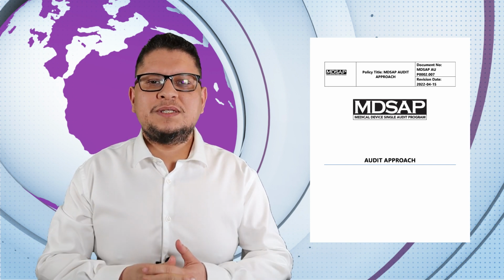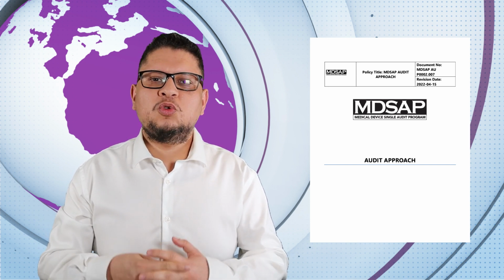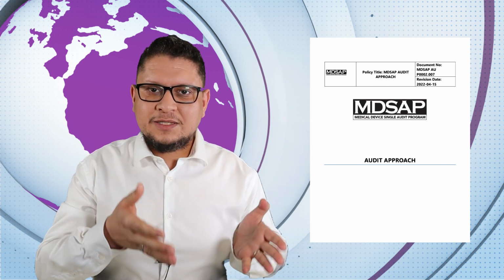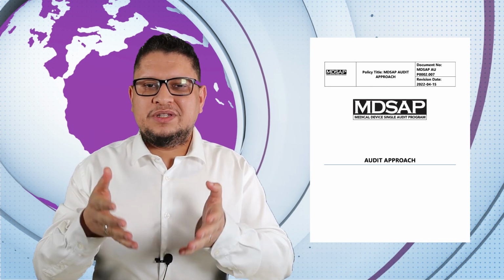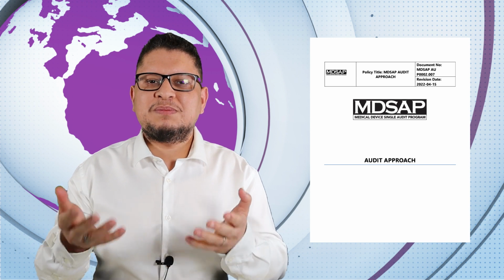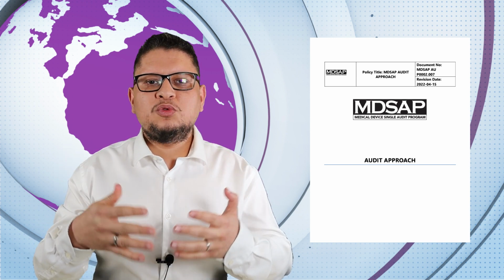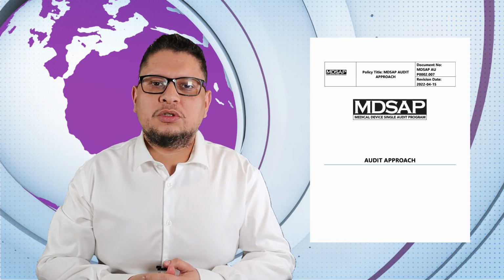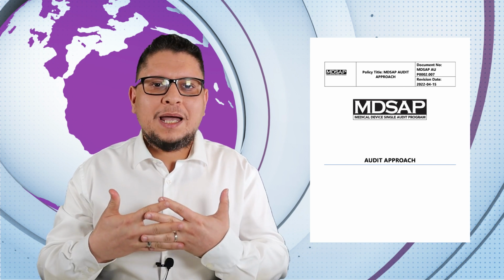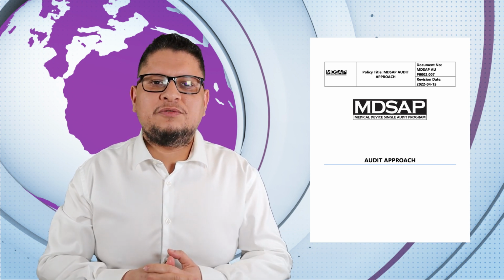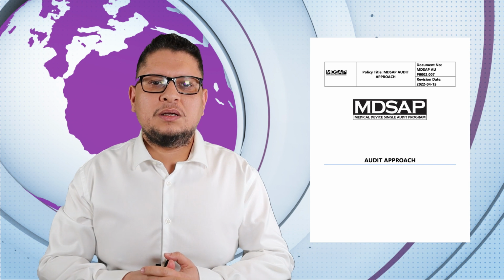If you have never used this document, it provides you all the requirements per ISO 13485, and per the different countries' requirements. There are some specific country requirements, and you can use that to verify if you are compliant or not. So this is really the tool I am using to audit companies for MDSAP. This is something that is really helpful.